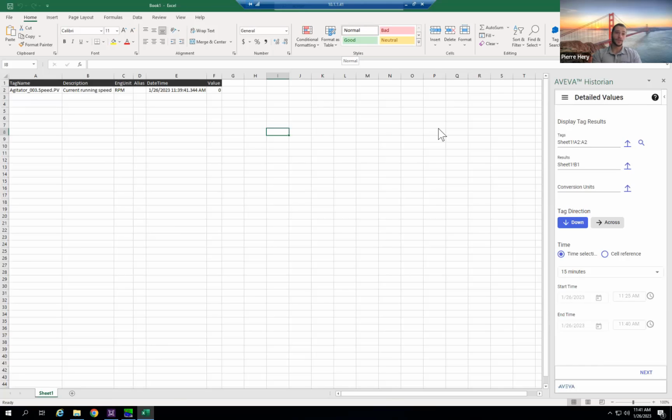And you can actually use those together. So now with 2023, you can replicate from the AVEVA historian to a Pi Data Archive if your Pi was sitting on your business network, for example. Previously, if you wanted a historian on your enterprise network, the architecture was a tier 1 AVEVA historian on your SCADA network and a tier 2 AVEVA historian on your enterprise network. Now you can have a tier 1 AVEVA historian on your SCADA network with a Pi Data Archive or Pi historian on your business network.